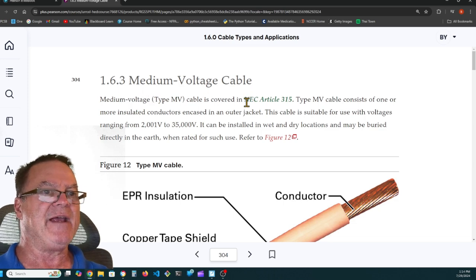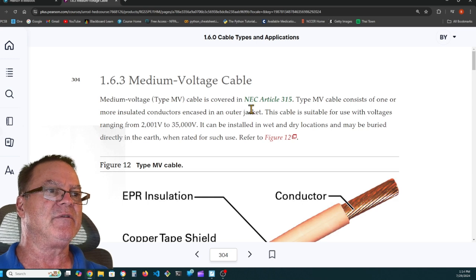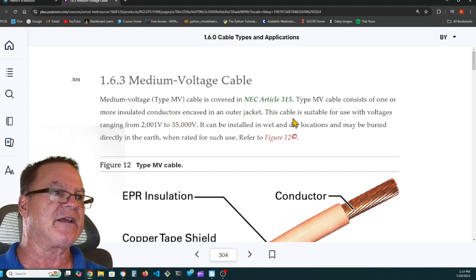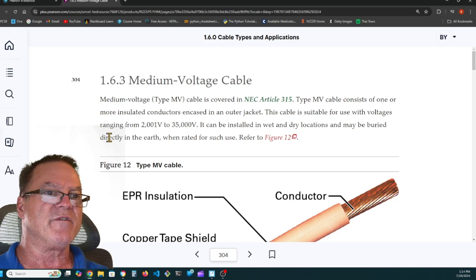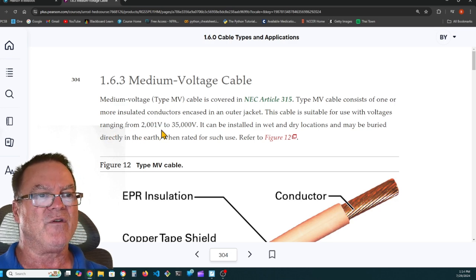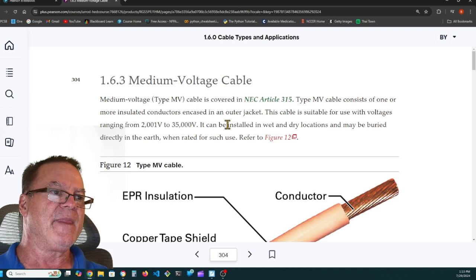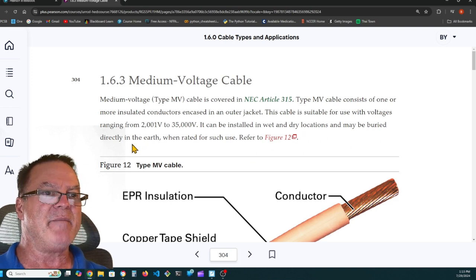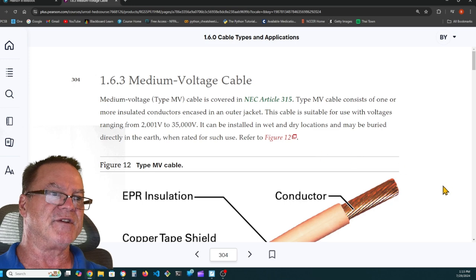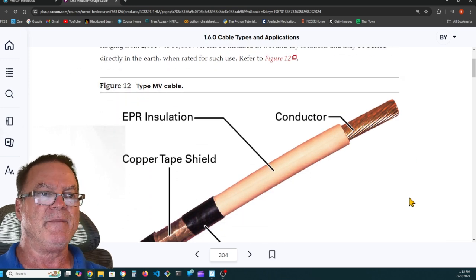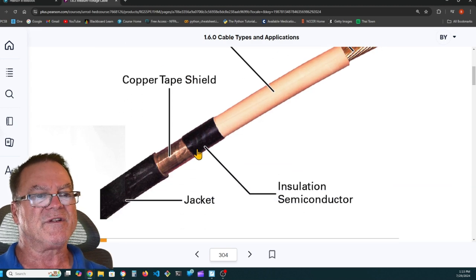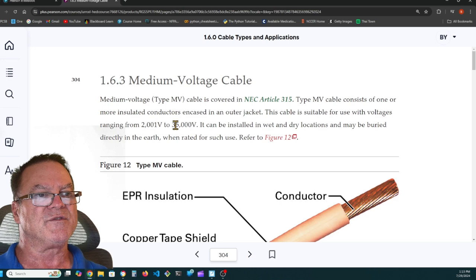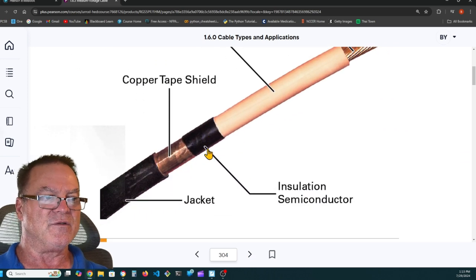1.6.3 Medium voltage cable. Medium voltage cable is covered in Article 315. Type MV cable consists of one or more insulated conductors encased in an outer jacket. This cable is suitable for use with voltages ranging from 2001 volts to 35,000 volts. It can be installed in wet and dry locations and may be buried directly in the earth when rated for such use. Refer to Figure 12. So, here's medium voltage cable. And notice how medium voltage is 2001 volts up to 35,000 volts.